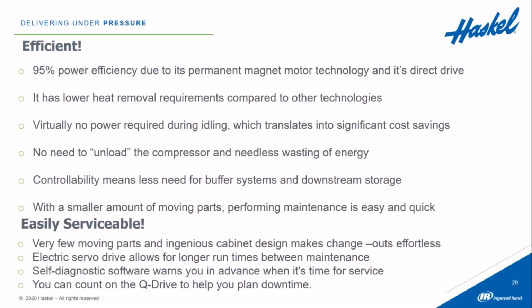QDrive's also efficient. 95% power efficiency due to its permanent magnet motor technology and that direct drive. It has lower heat removal requirements compared to other technologies. And as Dave mentioned earlier, there's virtually no power required during idling, which translates into significant cost savings. There's also no need to unload the compressor and needless wasting of energy. You can start QDrive up at a wide range of pressures, and that could be significant cost savings to you, so you don't have to worry about drawing that pressure all the way down and restarting the system.